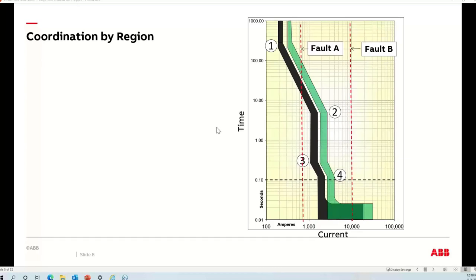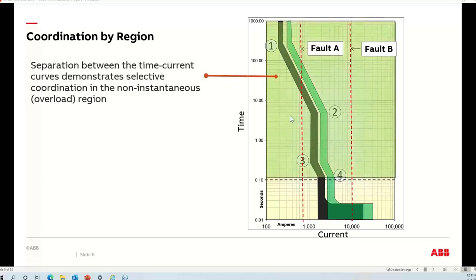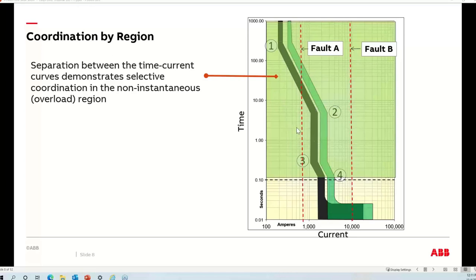There are two major parts to a time-current curve when we're talking coordination. I have two electronic trip circuit breakers laid side by side. The various numbers represent different break points between a pickup and a delay. Looking at the first shaded area — from approximately the point where I transition from short time to instantaneous — if I can separate the breakers from that point and above, I can say they're coordinated because I have 'white space' between them. This is the non-instantaneous region, or what some NEMA documents call the overload region — that's a separate technique to determine coordination.